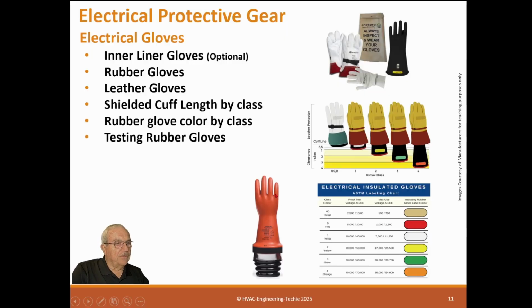Now, you have to test gloves every once in a while, and the code says every 6 months. You normally test them with air. You pump them up to make sure there are no pinhole leaks. A pinhole leak will actually allow an arc to enter into the glove. So we don't want that. So gloves are tested, and normally any utility or any electrical company will keep the gloves tested company-wide on a whole basis. And then anything that fails the test is replaced. They can't be repaired. They're replaced. So it's really critical. What they don't want you to do is trust a rubber glove that's no good, because that's the same as not having one.